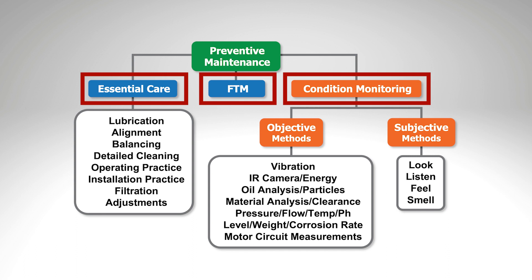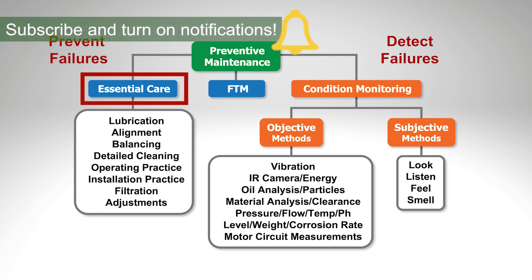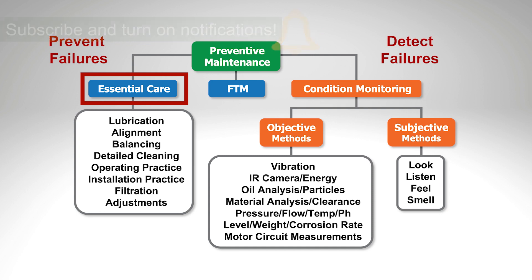We have three parts. On the left side we have prevent failures, and on the right side we have detect failures early. Essential care of equipment can prevent failures. Examples include lubrication, alignment of equipment and shafts, detailed cleaning of equipment, operating practices — how we actually operate equipment — installation practices, whether we have the right torque, whether we install bearings correctly or use a sledgehammer to put them on the shaft, filtration of air, water, lubricants, and adjustments. All these things directly impact the life of equipment.